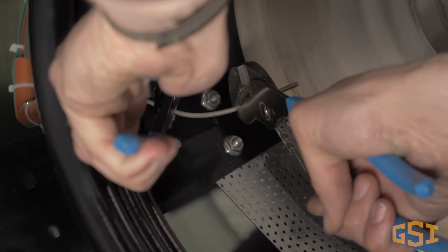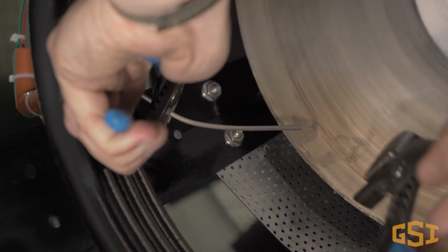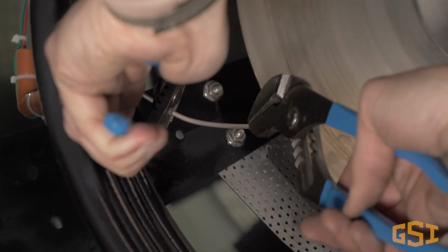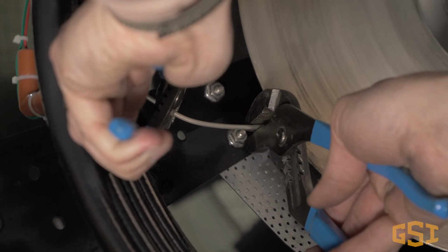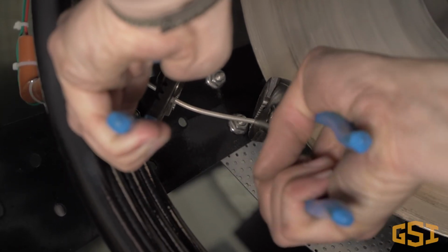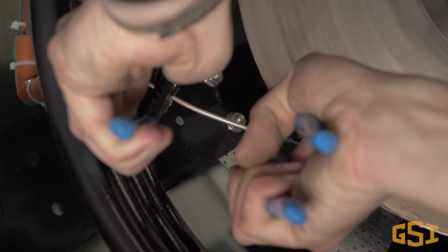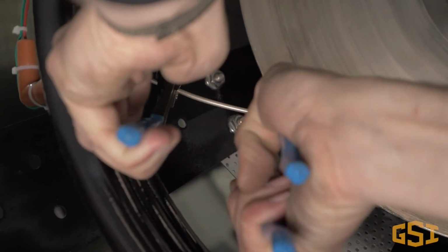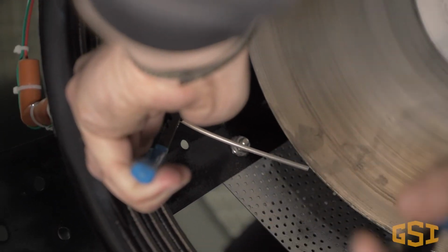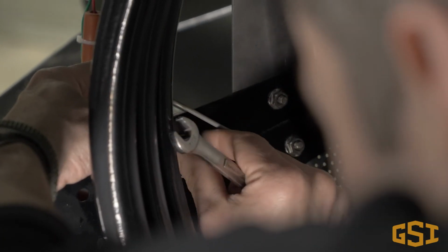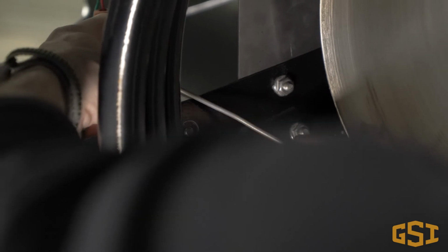The flame rod is very stiff, and the most often used method to adjust it is with 2 pairs of pliers. Here's an example of adjusting the flame rod. Another method is to change the location of the flame rod by turning the mount or totally relocating it. Your goal is to reposition the flame rod so it stays in constant contact with the flame. It is usually accomplished by trial and error.